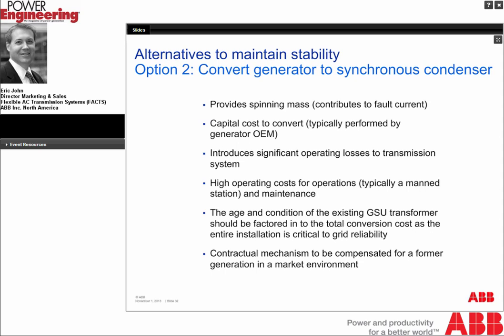Related to this, the GSU, the existing generator step-up transformer, should also be factored into the total conversion cost, because often if you convert to a synchronous condenser, you're taking an old machine, something that's been operating for 30 or 40 years, and you're extending the life. If the generator step-up transformer is of the same vintage, and you're doing a conversion to a synchronous condenser, the synchronous condenser becomes a critical piece of grid reliability, and the generator step-up transformer is a single point of failure potentially in that overall system, because it sits between the generator and the transmission network that the synchronous condenser is there to support. So another factor to consider. The third are the operating costs of a synchronous condenser.